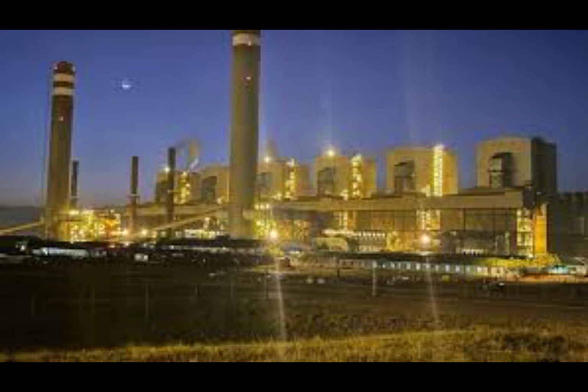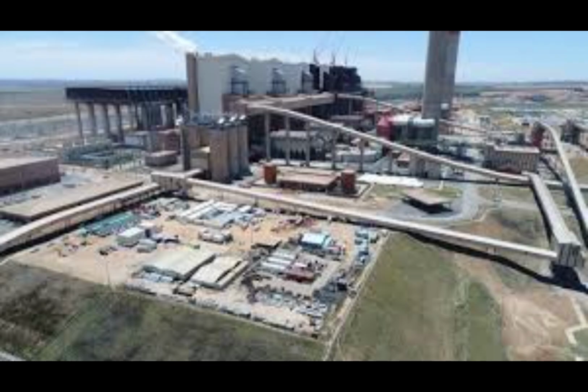systems, and filled with 128,000 liters of mineral oil. All electrical integrity tests were performed successfully to confirm that the transformer was ready to receive power. March 10, 2017. Unit 1 achieves commercial power. July 7, 2017. Unit 2 was synchronized to the national grid. March 16, 2019. Unit 3 was synchronized to the national grid.